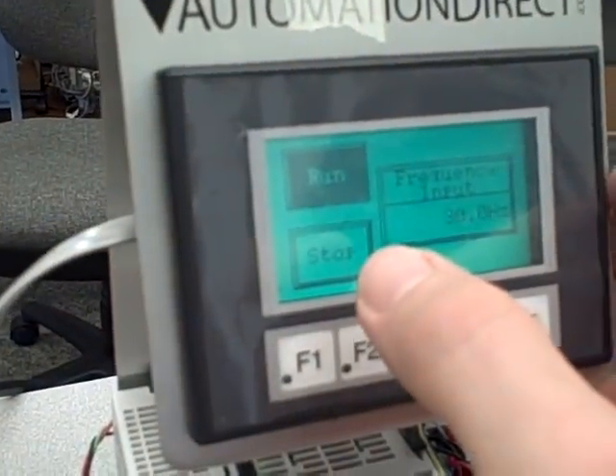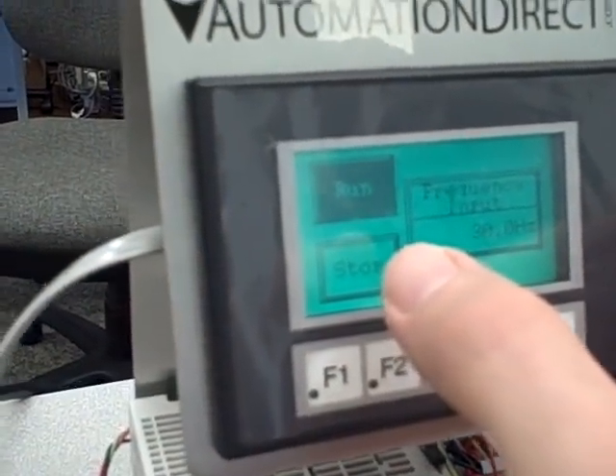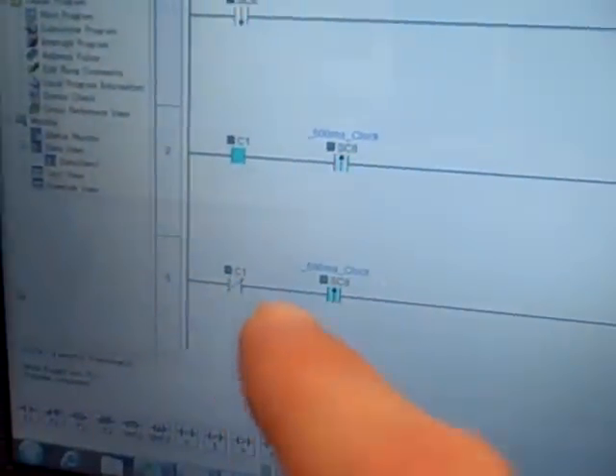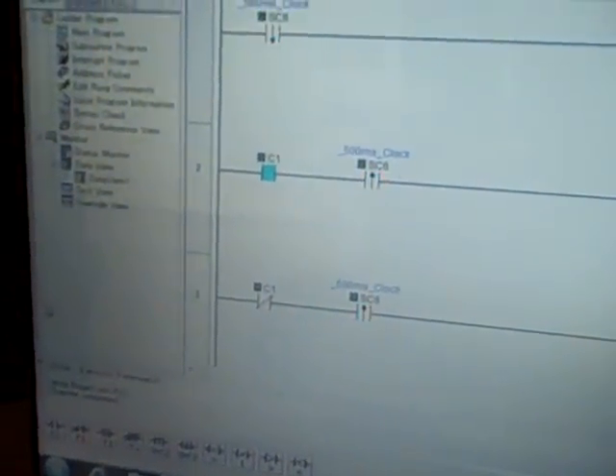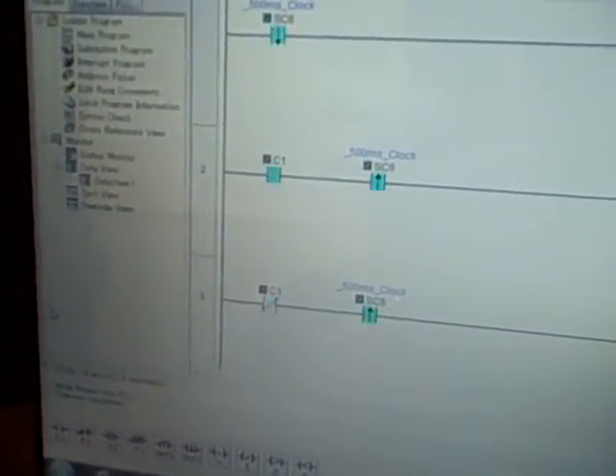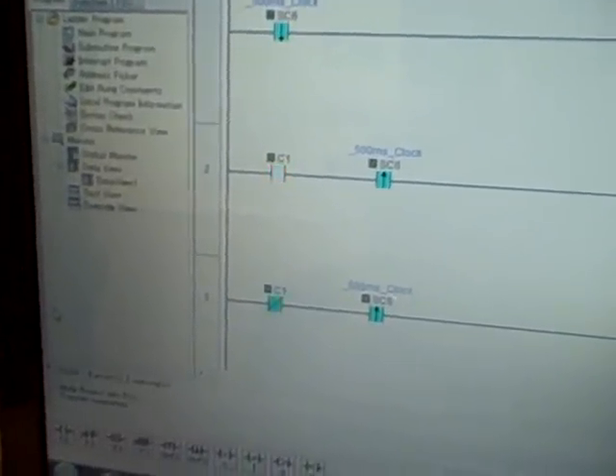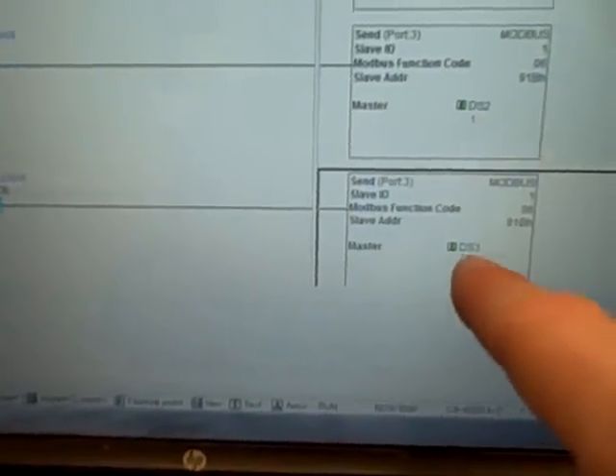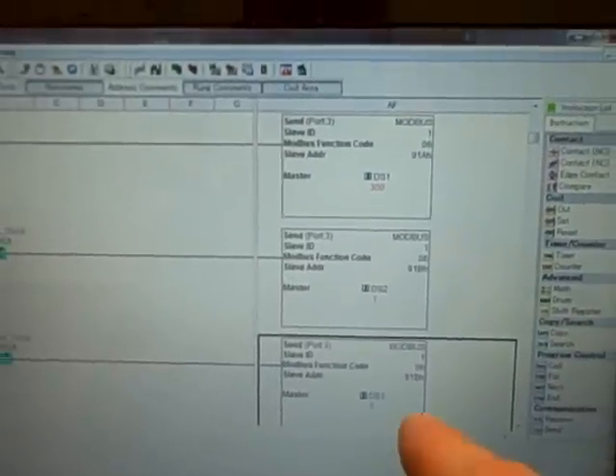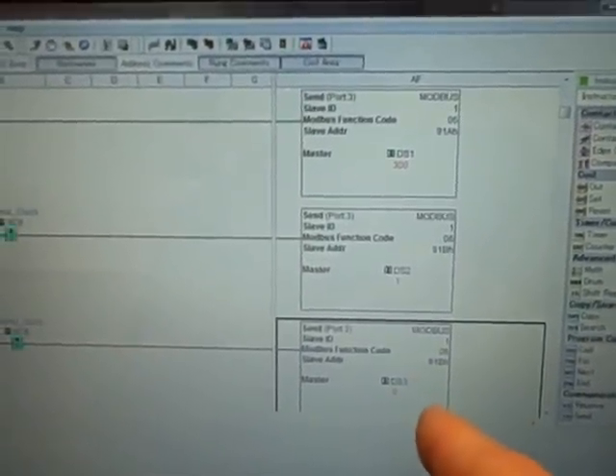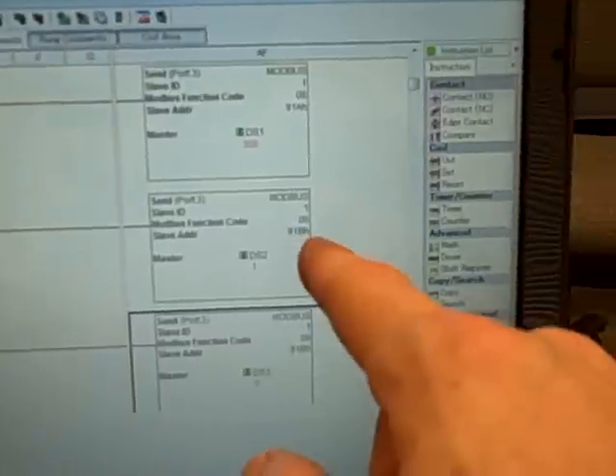If I hit the run or stop button on the HMI, it changes the value of the C1 bit. You can watch this as I hit the stop button and then the run button — you can see these two contact instructions change color. That's activating a different send instruction on the upstroke of the clock, sending a different value — either 0 or 1 — to that register that controls starting and stopping at the drive. In many other brands of VFDs that's actually a single bit you would write, but in this case it's a whole word we're writing to hex address 0x91B in the drive to start it and to stop it.